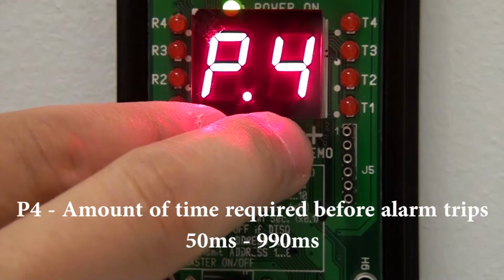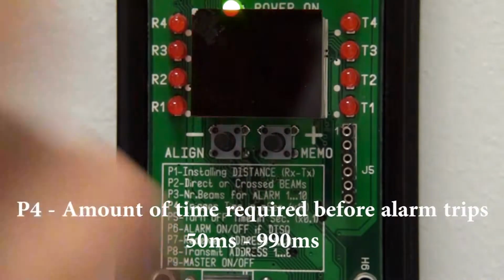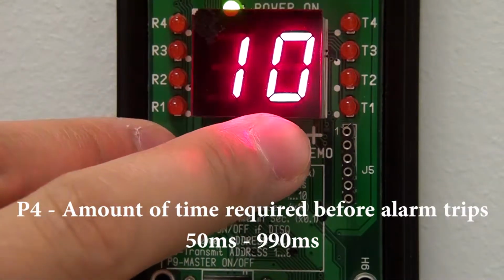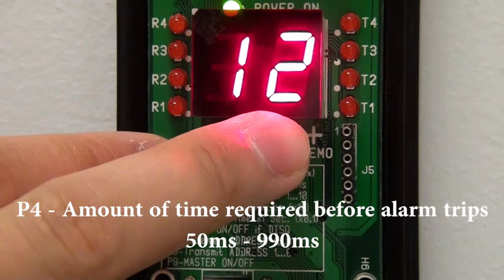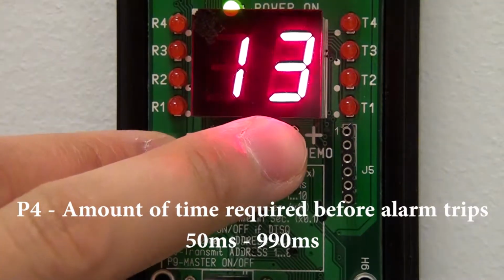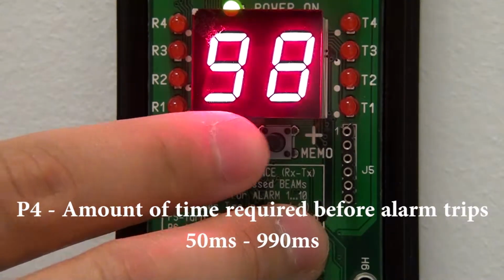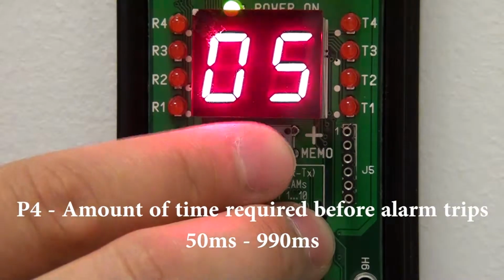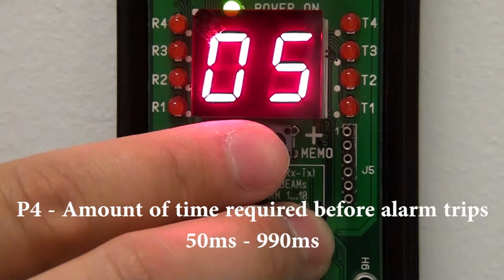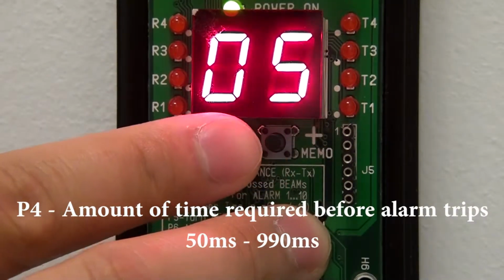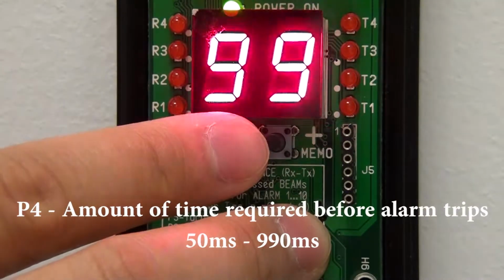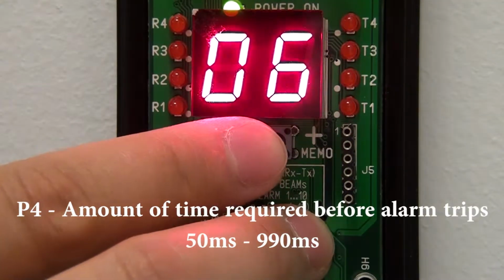P4 is the amount of time required before the alarm trips, and this is set in increments of 10 milliseconds. So 50 milliseconds would be 5. If we wanted to have it 990 milliseconds, it'd be 99.